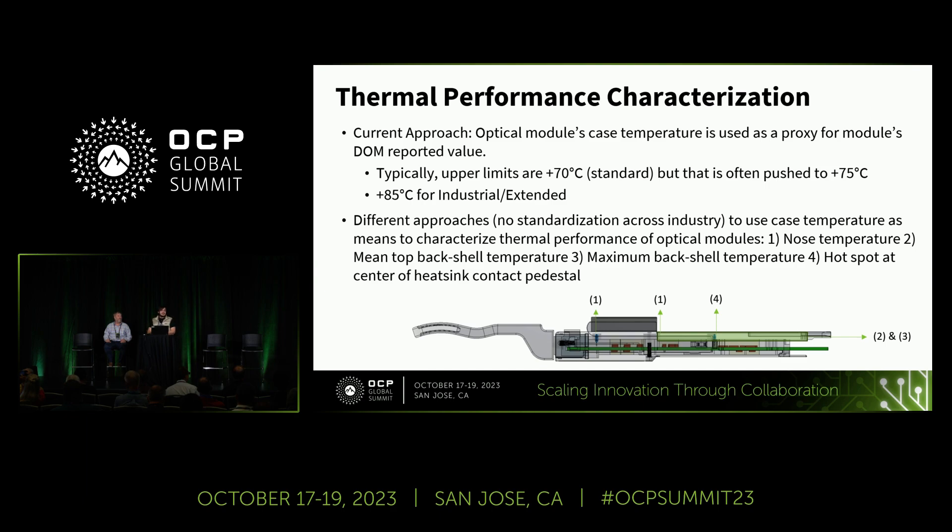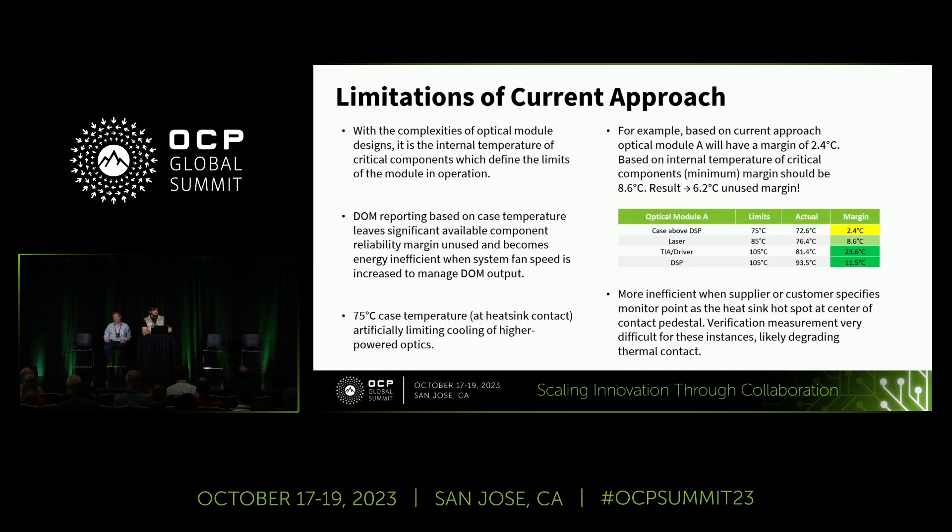However, there are different approaches regarding where exactly that monitor point is placed on the case temperature, and there is no standardization across the industry. Amongst the more popular locations are the nose temperature at location 1, the mean top back-shell temperature, the maximum back-shell temperature, and the hotspot at the center of the pedestal. There is no standardization on where on the case we should probe the module to determine case temperature — and that doesn't even address the margin issues even if we did standardize the monitor point location.